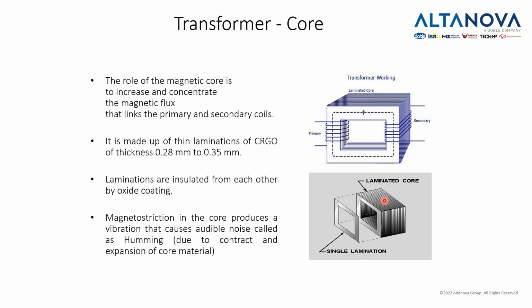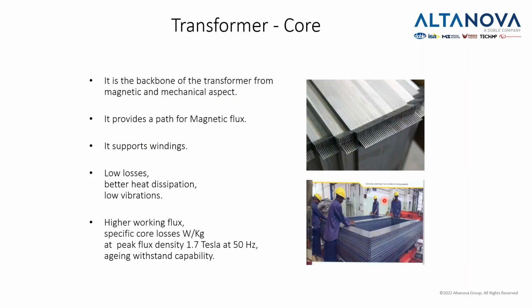The role of the magnetic core is to increase and concentrate the magnetic flux that links the primary and secondary coils, and it is made of laminations, which are insulated from each other by an oxide coating in order to reduce the losses, in order to reduce the eddy currents. Now, moving on, the core, as you can see here, looks like two windows, but you can see that effectively these are laminations. So the core is the backbone of the transformer from the magnetic and mechanical aspect.